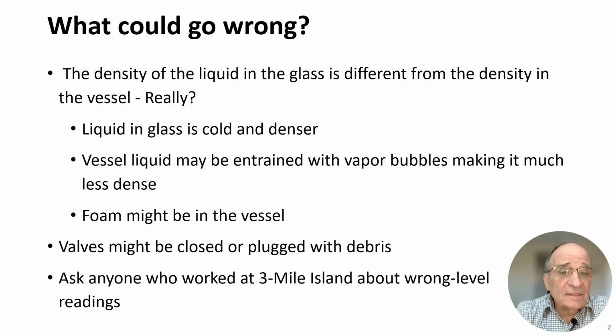What could go wrong? The density of the liquid in the glass is different from the density in the vessel. Really? How could that happen? Well, the liquid in the glass might be cold and denser, or the vessel liquid may be entrained with vapor bubbles, making it much less dense. Foam might be in the vessel. This is very common in amine systems where, let's say in the amine absorber, you have a foam level on top of your liquid level. Well, that's certainly going to give you a false reading. Valves might be closed or plugged with debris. Ask anyone who worked at Three Mile Island about wrong level readings, and they will give you an earful.